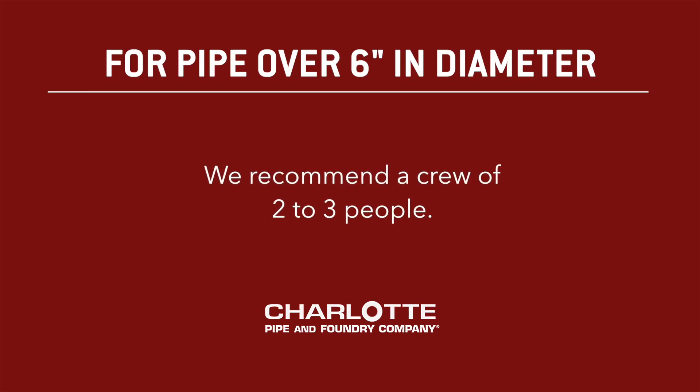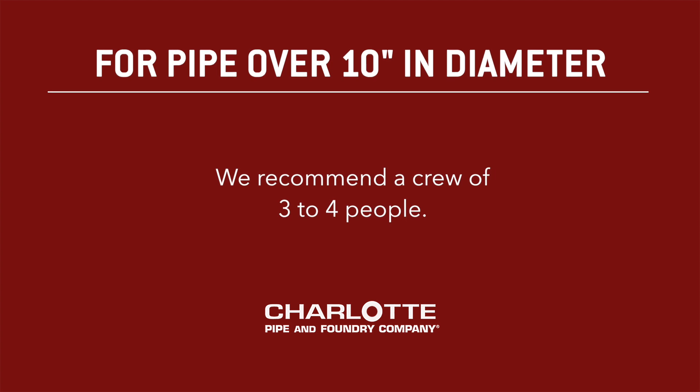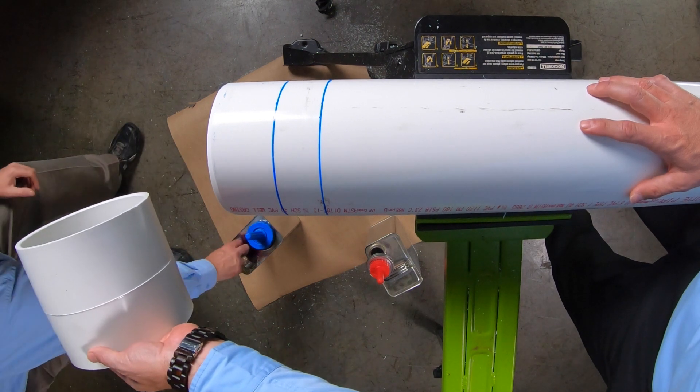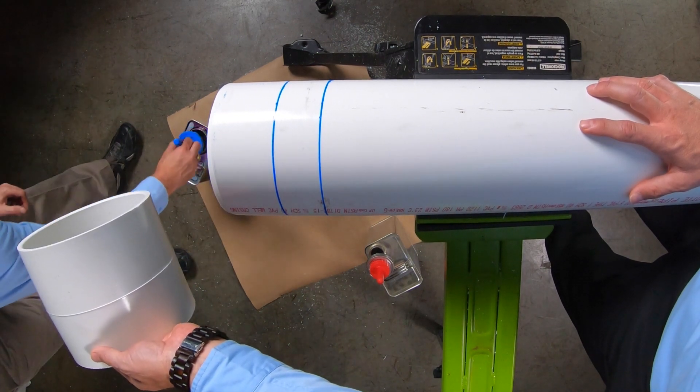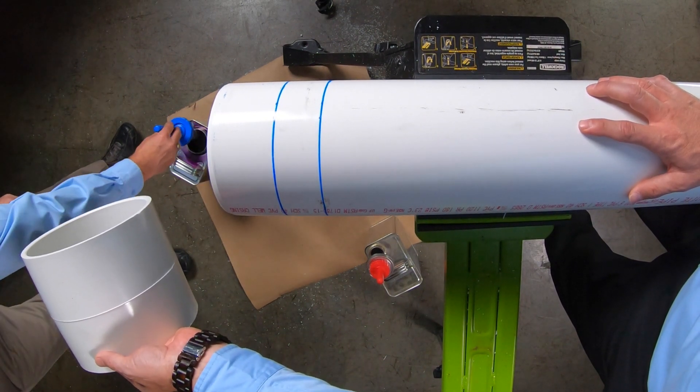With pipe over six inches in diameter, we recommend a crew of two or three people. For 10 inches and larger, a crew of three to four people. Even if you could manage to do this yourself, it is difficult, if not impossible, to put the joint together before the primer and cement begin to set.